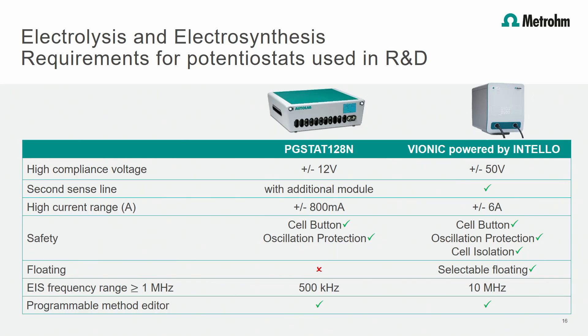To show how a suitable potentiostat is chosen for electrolysis and electrosynthesis experiments, I compare two instruments from our product portfolio: the PgStat128N with Vionic, according to their specifications. There are three main advantages of Vionic at first glance: plus/minus 50V compliance voltage, 6A maximum current, and a maximum frequency of 10 MHz, covering a wide range of applications. To conclude, Vionic fits much better to electrolysis and electrosynthesis applications than the PgStat128N.